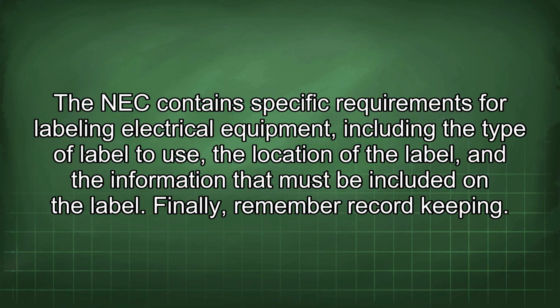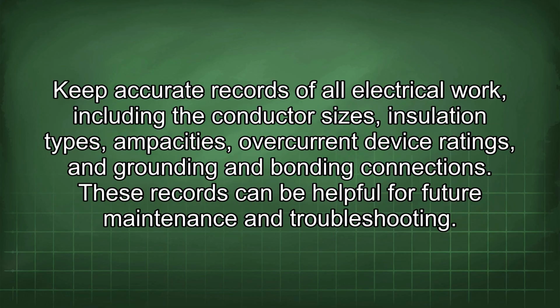Finally, remember record keeping. Keep accurate records of all electrical work, including the conductor sizes, insulation types, ampacities, overcurrent device ratings, and grounding and bonding connections. These records can be helpful for future maintenance and troubleshooting.